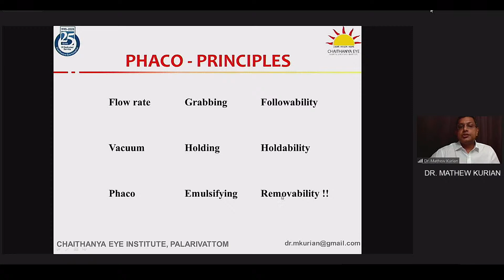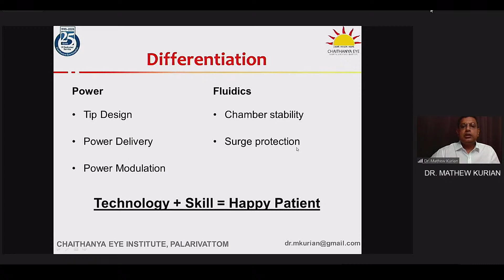Essential phaco principles: flow rate is followability, vacuum is holdability, and phaco is the ability to remove those fragments. The differentiation today is not so much on the power side. Tip design, power delivery and modulation are all very advanced. The differentiation between machines, I think, is in the quality of fluidics, the chamber stability and the surge protection that is given. Together, you can give a happy patient.